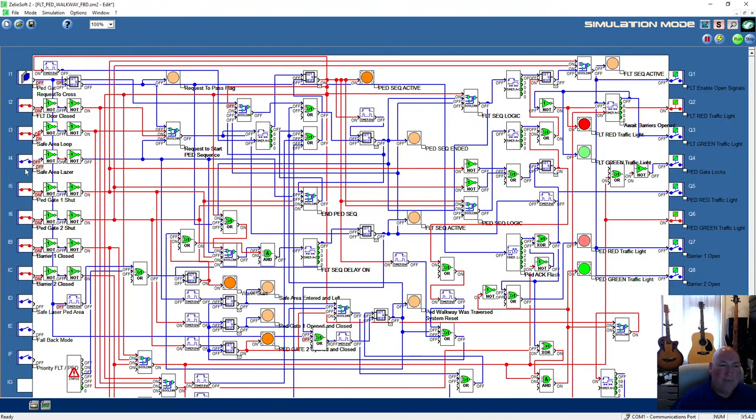Now, if they're walking across, both gates are shut. If somebody was to barge the forklift truck door by the control panel, or somehow lift it up physically, or if... this is where it gets complicated. At the minute, in this mode, fallback mode is off, so it is the full safety mode.